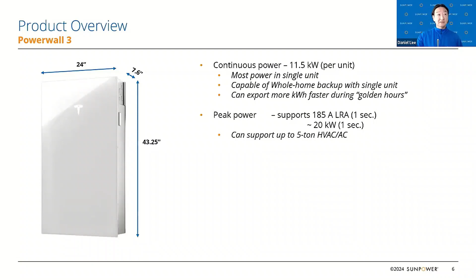However, keep in mind, in our modeling, 185 amps of LRA, that's a large amount of inrush current. And we actually model 185 to be up to a 6-ton unit. So in other words, this is a product that can support a 5-ton HVAC or AC unit without soft start. So no soft start is necessary to be able to support an AC or HVAC unit of that size.